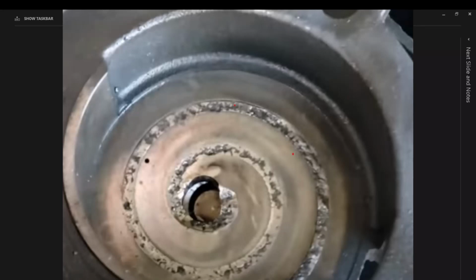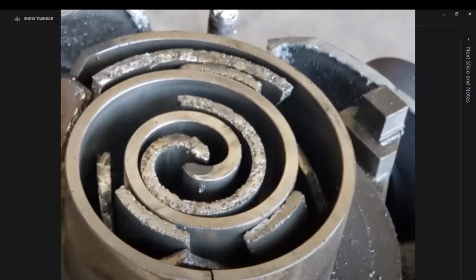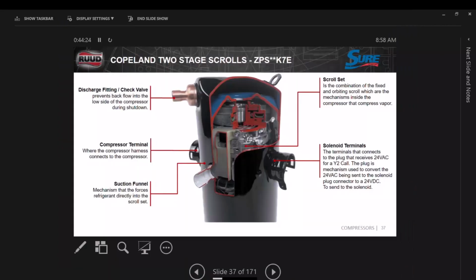This is what the scroll looks like. There's two plates. One that goes over the top of this and this one. And whenever you introduce liquid into it, the other one looks like this now. And you're going to get all these little pieces falling out of that compressor into your suction. That is from liquid floodback right there. And it didn't take long to do it. That stuff will fall down into the suction funnel and out into your suction line. Not knowing it, you change the compressor, you start it up, and one of those pieces goes into the scroll plate. Now we just killed another compressor. So I'm going to tell you, always make sure there's nothing in that suction line if this ever happens.